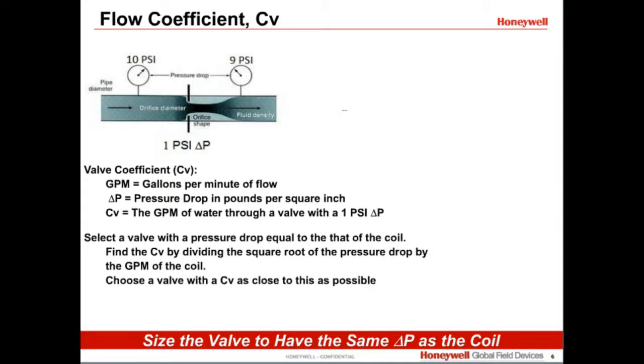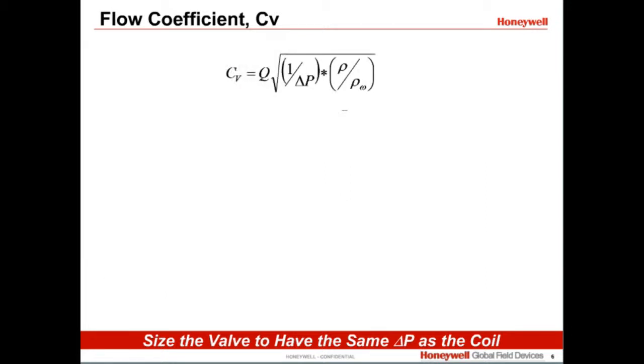To do this, calculate the CV using the GPM through and the pressure drop across the valve. The mathematical equation for CV is shown here, where Q is the rate of fluid flow in gallons per minute. The delta P is the pressure drop between the inlet and outlet port, and the rho divided by rho is the density or specific gravity of the media. Since these are HVAC applications, the media is probably water, with a specific gravity of 1. So this drops away from the equation.